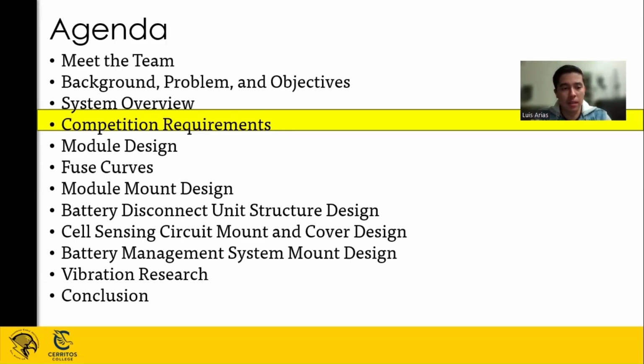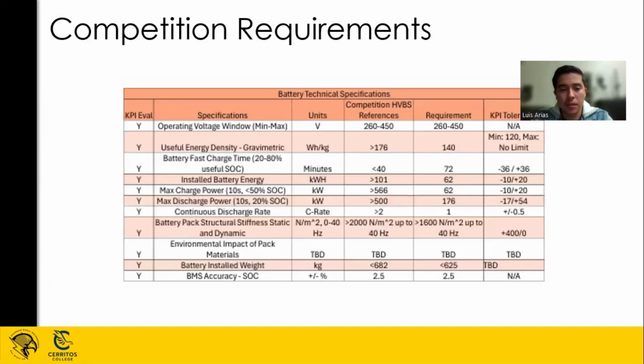Hello, my name is Luis, and I'll be going over the competition requirements. So here is a table of the competition requirements that we must focus on meeting. Our main requirements that we're focused on is the operating voltage window, which is to be between 260 to 450 volts. Our next important requirement is the installed battery energy, which is 62 kilowatt hour. And then also our continuous discharge rate of 1C rate. This will allow us to focus on how to size up our bus bars. And lastly, our battery installed weight, which has to be below 625 kilograms.